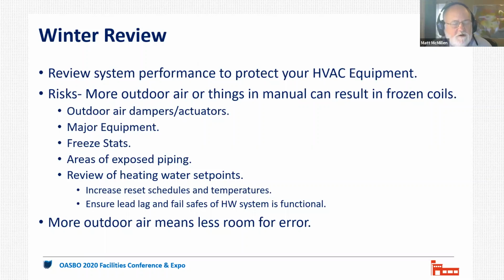If I could add something in here, Lucas, is not just stress testing or testing the operation of the freeze stats, but also being cognizant of anything that you've done in the past with nuisance freeze stat trips. Have you taken measures in previous winters to avoid that, and what's the impact of that on how much fresh air you can be bringing in? Are we going to have to look at things like stratification to address any issues that would prohibit you from bringing in additional outside air?